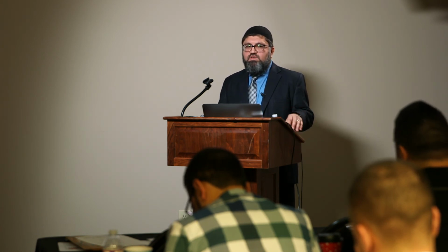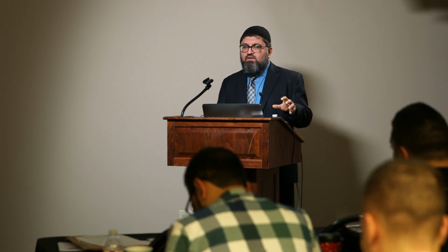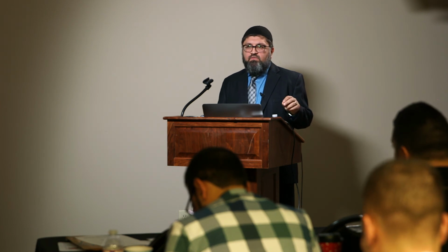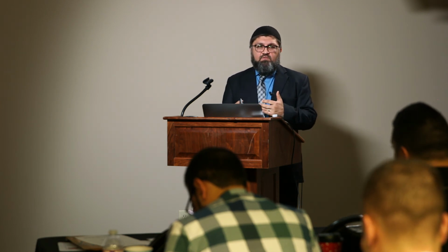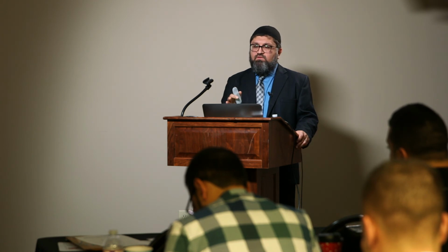But we have to have a trigger EMG, and trigger EMG is not a regular 2.7 hertz. It has to be more than 100 or 200 hertz stimulation. And many times the implant people are there, but they are not using the correct stimulation parameters, and don't get a response. So you have to have about 110 to 200 hertz stimulation, and you can get a very good response.